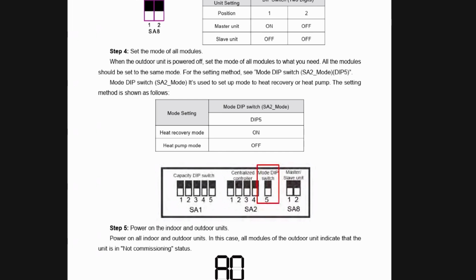So for the information we're going to cover on all the dip switches, it's important to note that this has to be done with the power off to the outdoor unit. Yep, I said that yesterday in yesterday's broadcast, about every broadcast I've ever done. Anytime you are changing dip switches, it has to be done with the power off. The boards recognize dip switch changes at power up. So, just a golden rule. If you always follow that rule, no matter what you're working on, you don't have to worry about it.